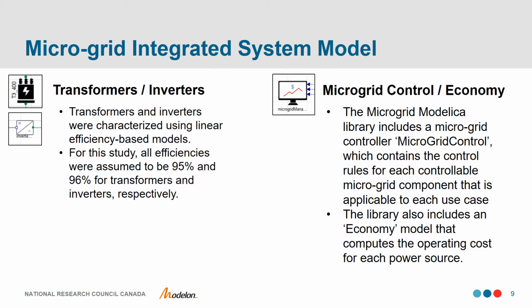The transformers and inverters required by the system were characterized using linear efficiency-based models. With respect to control and economic analysis, the microgrid manager includes both a microgrid control element as well as an economy model, which can compute the operating costs for each of our power sources.